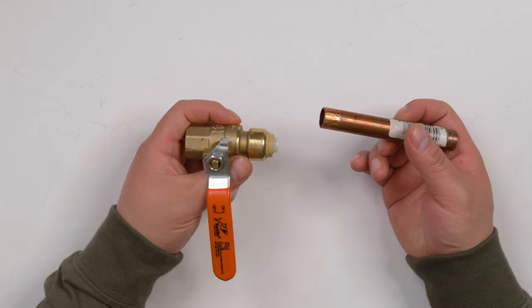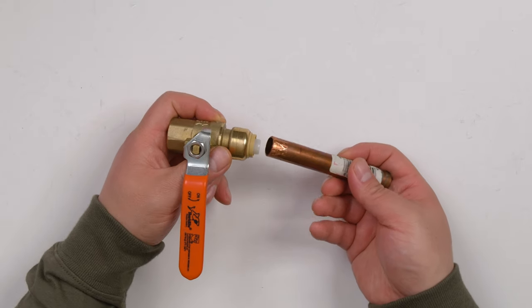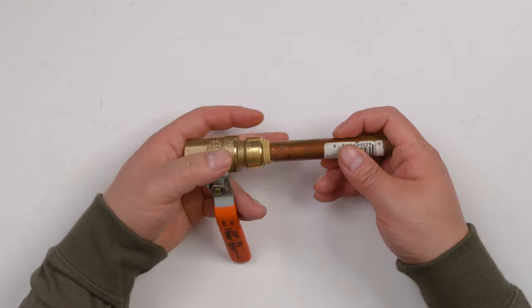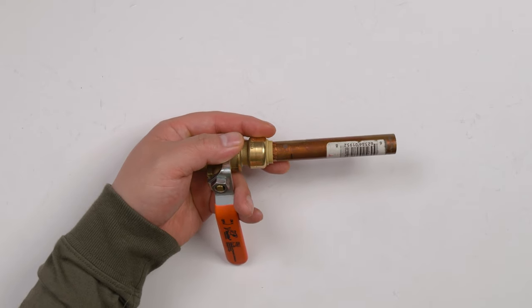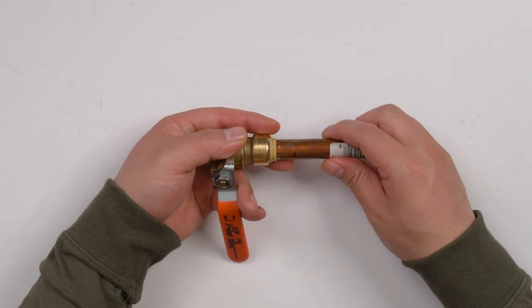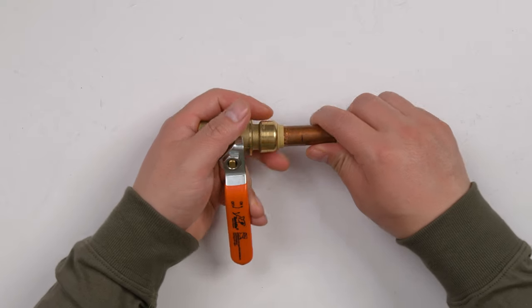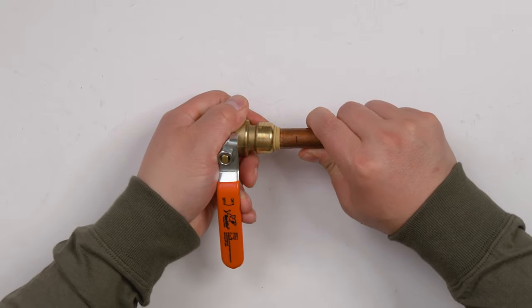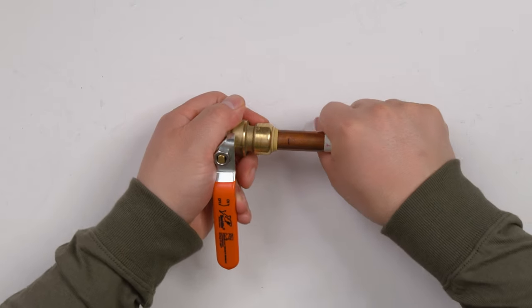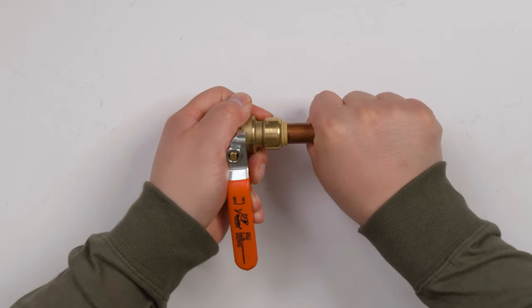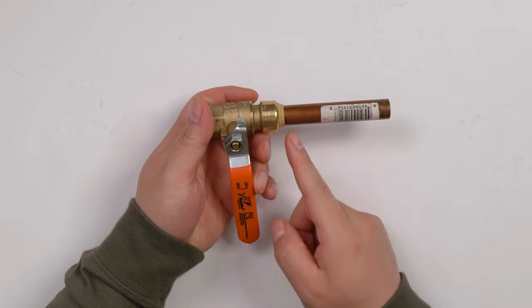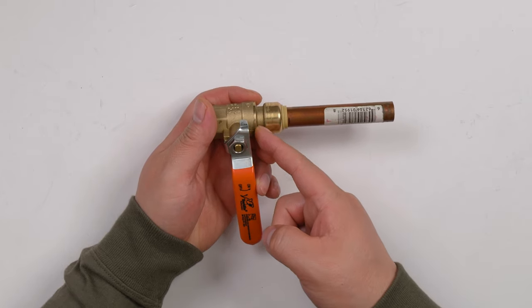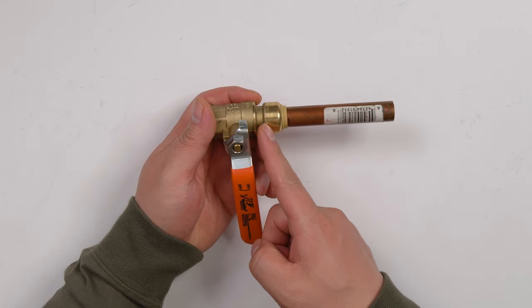So when you get ready, first step: put the inner collar in the tube like this. Then you will be against the stainless grab ring. Line it up—it must be lined up—and start to push. Keep pushing. Okay, right here. So the mark is here. You see that it's all the way in, so it will get a good seal.